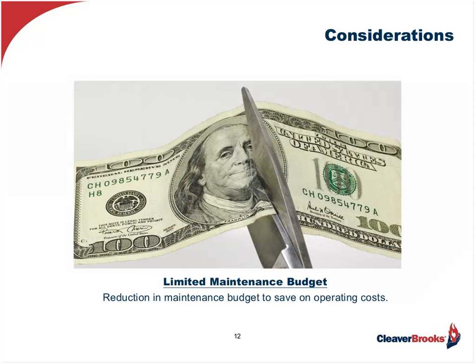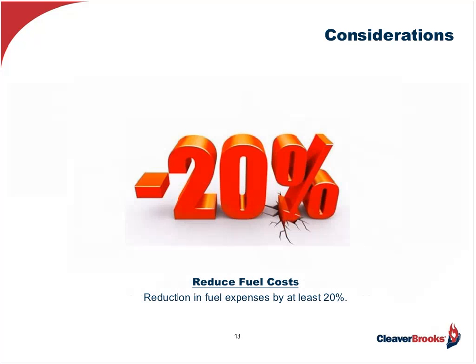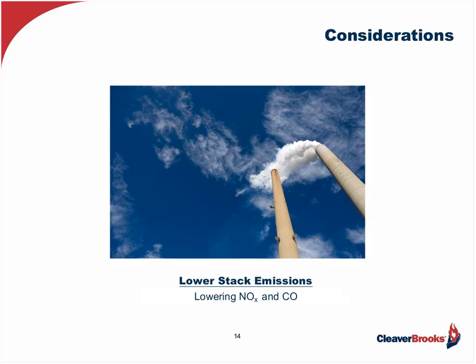They're cutting the maintenance budget by reducing staff and keeping costs as low as possible. They want to reduce fuel costs by a minimum of 20%. At the same time, they need to reduce NOx requirements to 20 parts per million — as mandated for their locale and capacity — but are looking at getting down to as low as 9 parts per million or less, then selling those emission credits on the open market to reduce operational costs. They also want to hold CO at 50 parts per million or less, ideally zero.